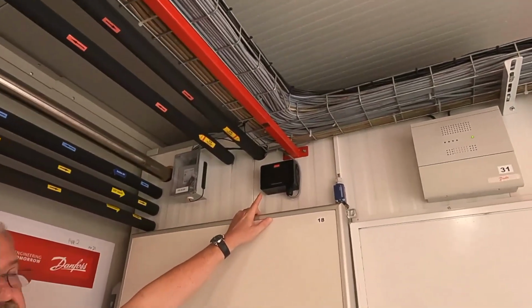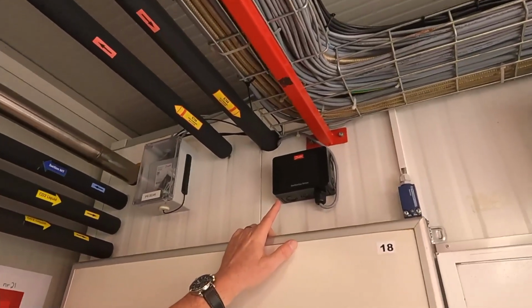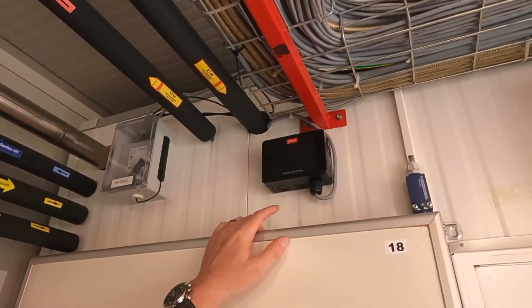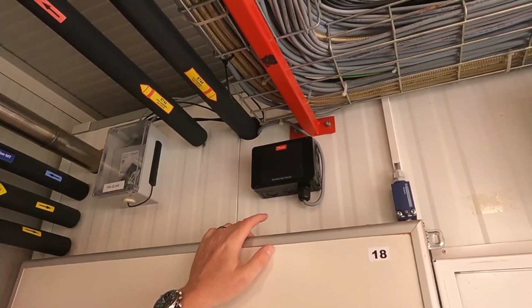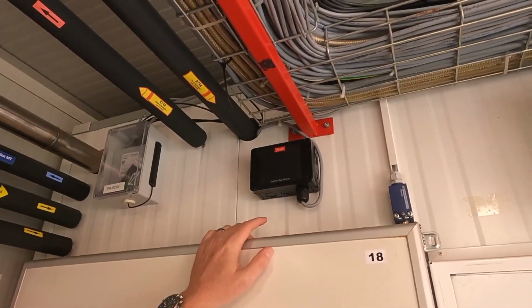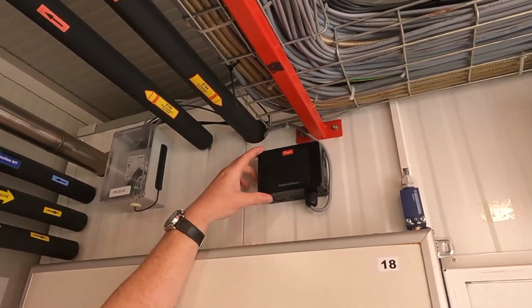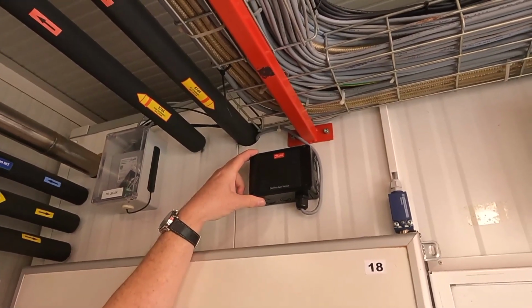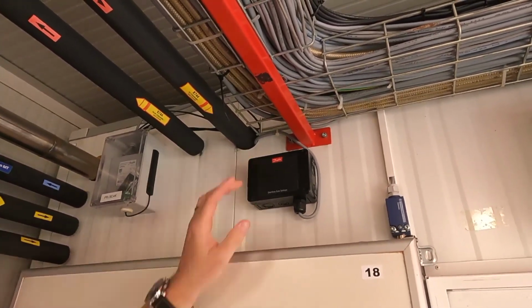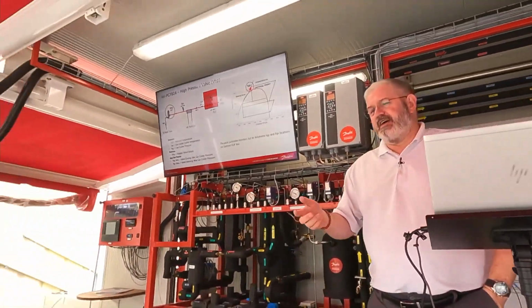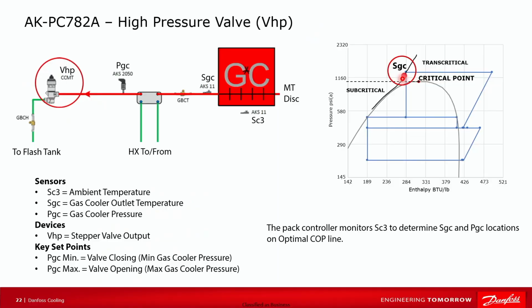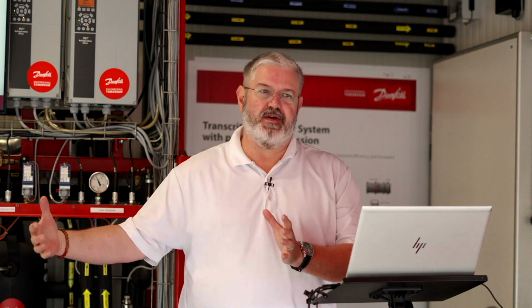So this is our DGS gas sensor. It's basically our CO2 sensor. Typically, you're going to have one mounted low on any refrigeration system. So as a Danfoss employee, I would recommend this gas sensor if you're looking for leak detection that's permanent. If you're looking for a wand leak detector that you walk around and sniff the system with, I'll be honest, I'm not familiar with the different categories. The only times I've done that, I borrow it from the contractor. So my recommendation is borrow it from your friend.